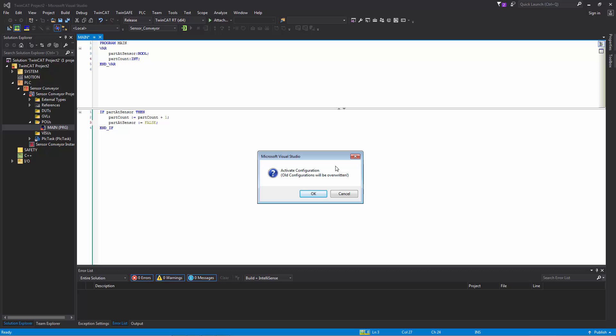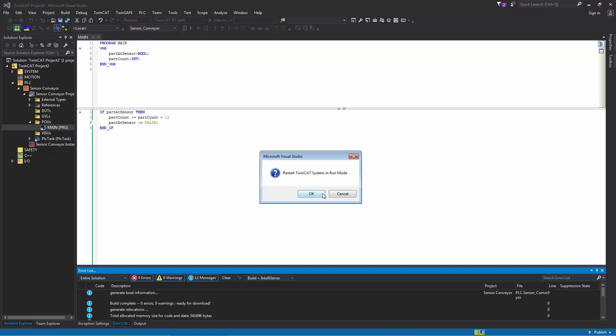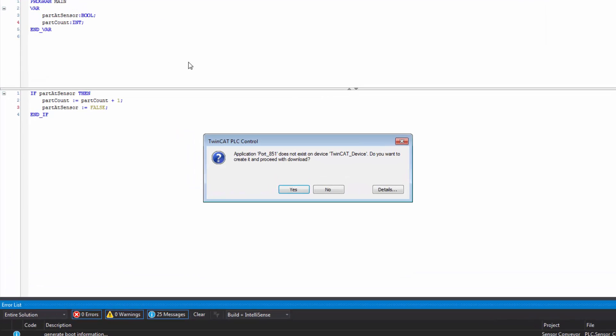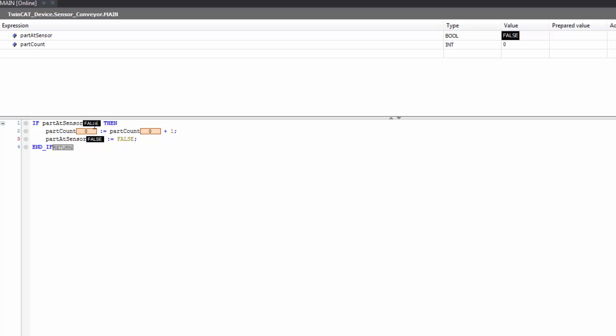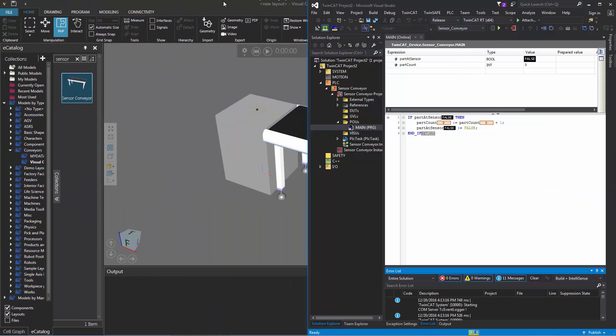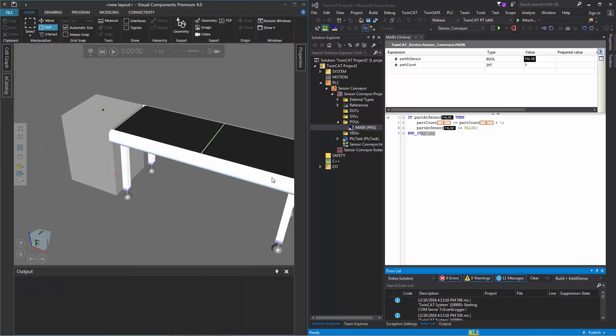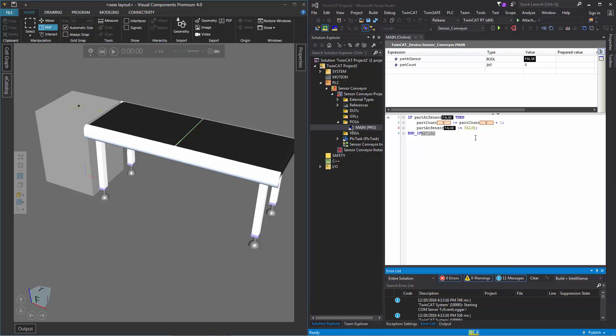It's just a matter of following the prompts given to you by Visual Studio — I'll click OK. In some cases you might be prompted to enter a license, so follow the prompt and continue on. I'll click OK to enter run mode. On the toolbar I'll click this icon to log in. I get a prompt letting me know my PLC is running on port 851, so I'll click yes. Notice here are the values of our variables — part_at_sensor is false and our part_count is at zero. Let's move the project to the right side of the screen and Visual Components to the left side, and unpin the panels to get a better view. Now we need to establish a connection between this simulation and this PLC.